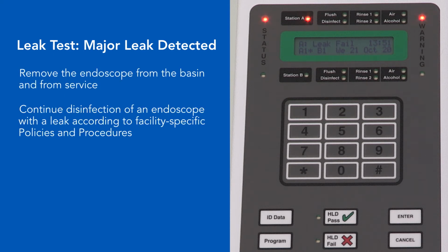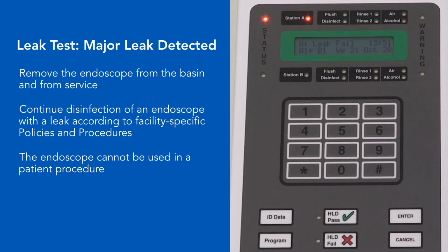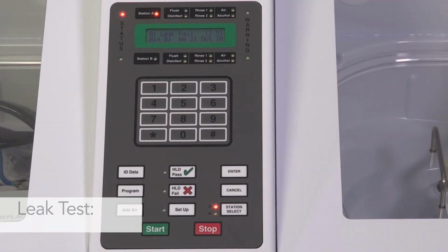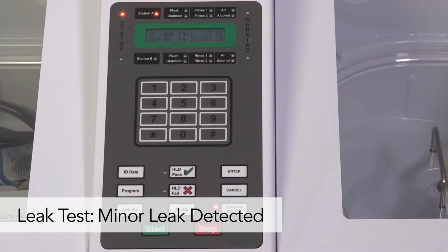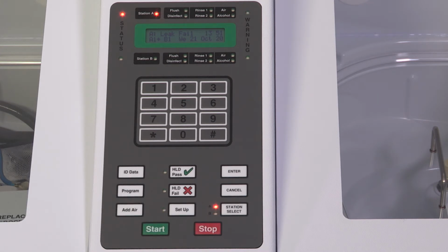Continue disinfection of the endoscope with the leak by following your facility's policy and procedures. This endoscope cannot be used in a patient procedure and must be sent out for repair. If there is a minor leak and pressure can be maintained within the endoscope, the DSD EDGE Reprocessor will continue to monitor and disinfect the endoscope.